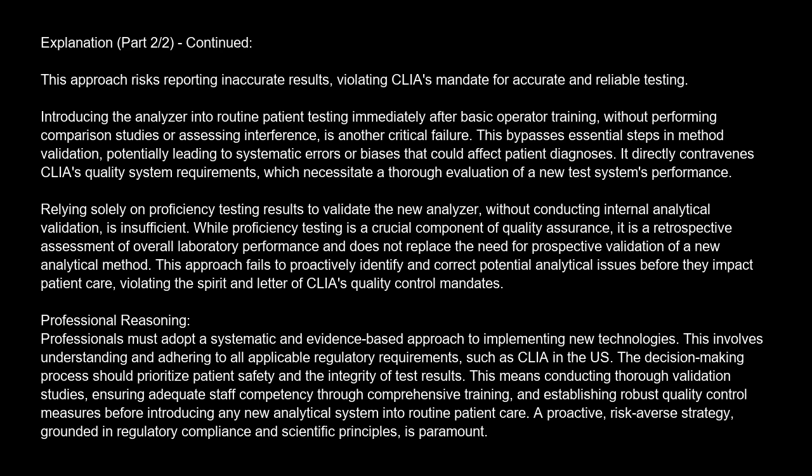Introducing the analyzer into routine patient testing immediately after basic operator training, without performing comparison studies or assessing interference, is another critical failure. This bypasses essential steps in method validation, potentially leading to systematic errors or biases that could affect patient diagnosis. It directly contravenes CLIA quality system requirements, which necessitate a thorough evaluation of a new test system's performance.